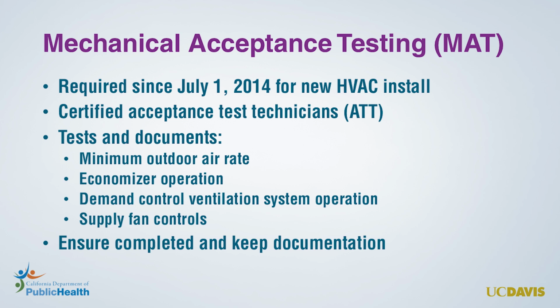With regard to indoor air quality, mechanical acceptance testing includes testing and documentation of the minimum outdoor air rate, economizer operation, demand control ventilation system operation, and the supply fan controls. Unfortunately, this testing is often overlooked.